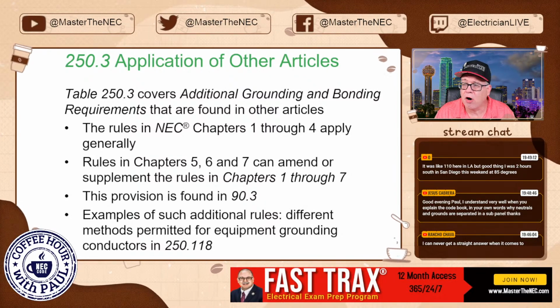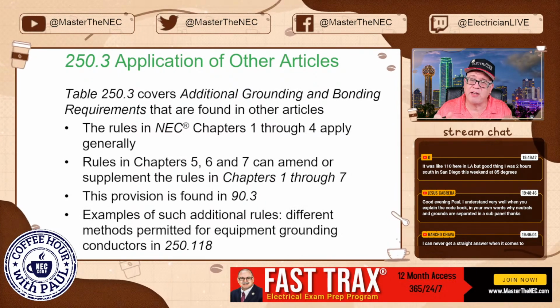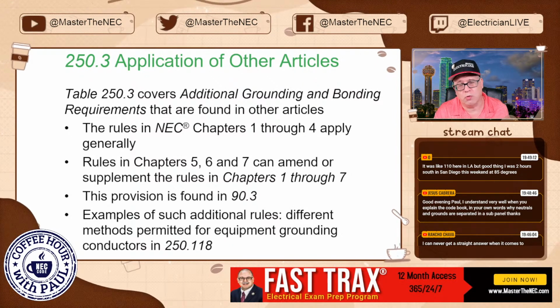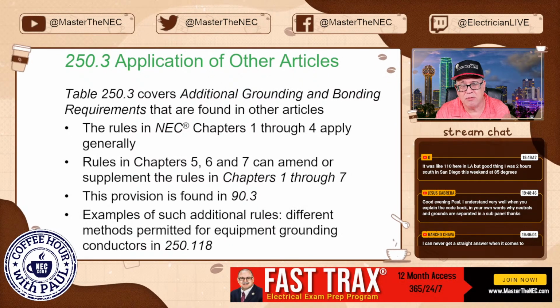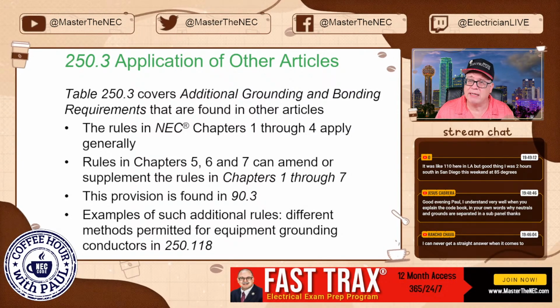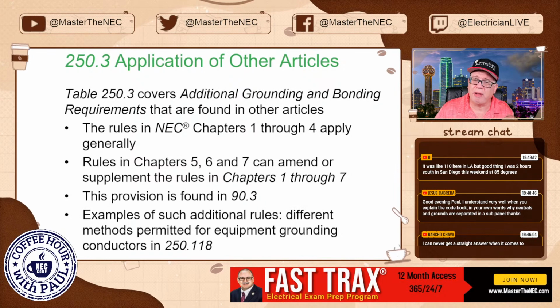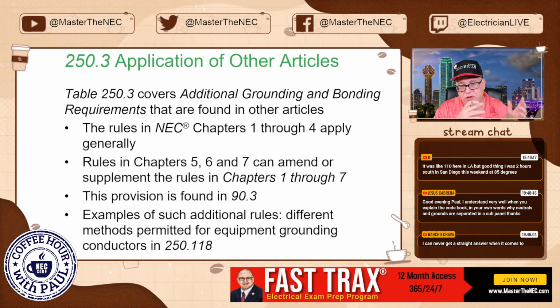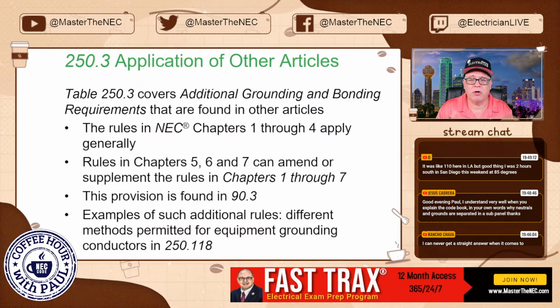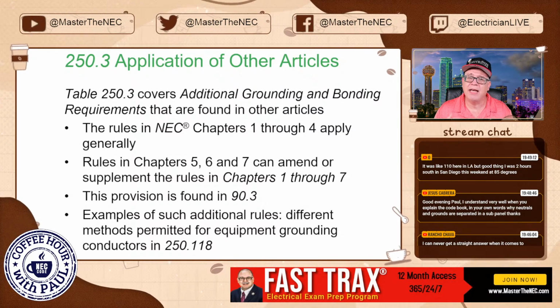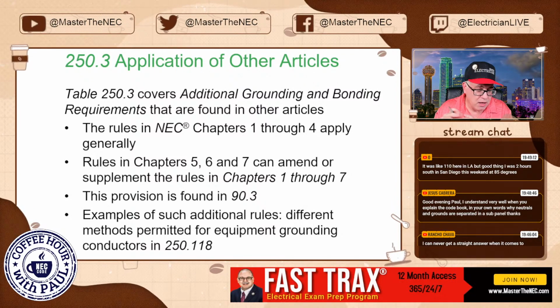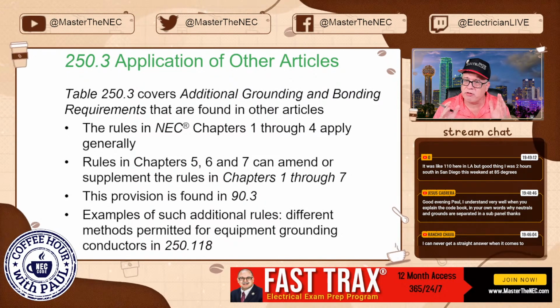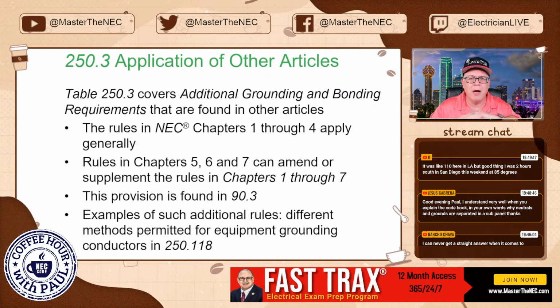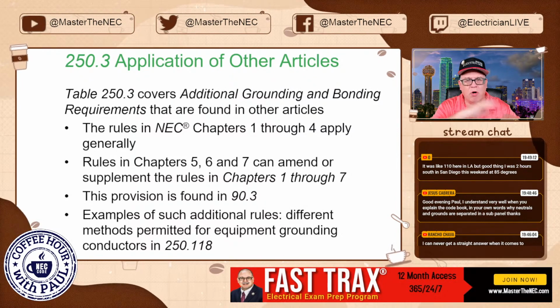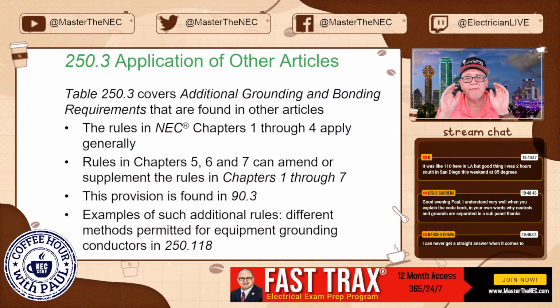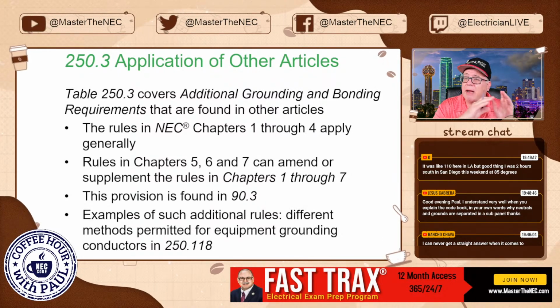Another example would be Article 680, and let's say Section 26 for equipotential bonding. So you've got our rules in Article 250 that we have to follow, but then you get up into 680, and guess what? It's going to modify or supplement something that was in Chapter 2, but now you're up in Chapter 6, and it's going to modify or supplement it. And that's what the code can do. And that is all found in the code in 90.3. And I think so many people fail to go look and see that structure. And just remember, chapters 1 through 4 in the code apply broadly. 5, 6, and 7 modify and supplement anything in chapters 1 through 7.